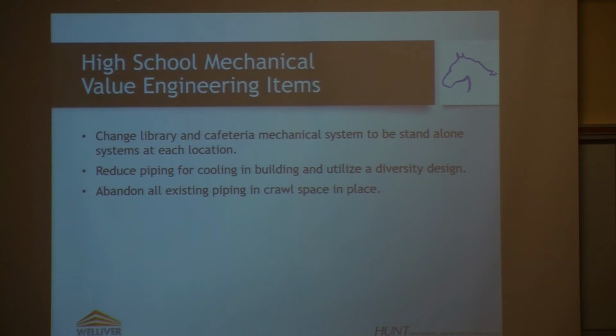A couple of things we've done relate to the library and cafeteria. Originally, those were going to be on the building-wide chiller system for cooling and heating. But because that required a lot of additional piping to be run throughout the building, we decided to take those two spaces and put them on their own standalone mechanical systems, adding air handling units at those locations. Believe it or not, the cost of those units is still less than the cost of the piping, because we were able to reduce piping size and eliminate some piping throughout the project. So the $50,000 to $80,000 spent on one of those units was significantly offset.